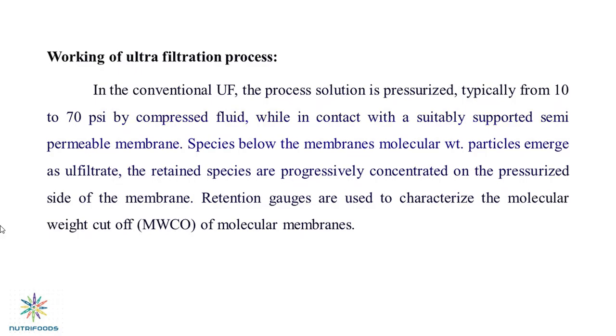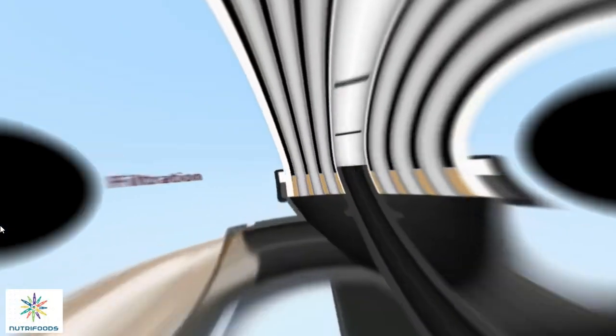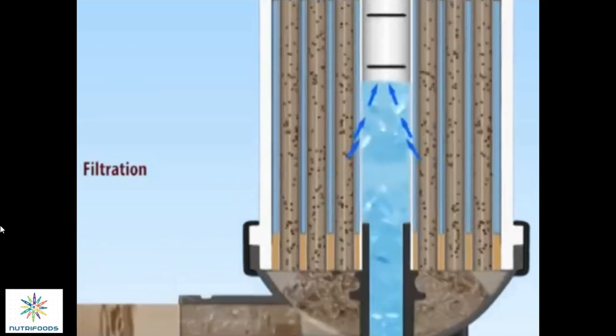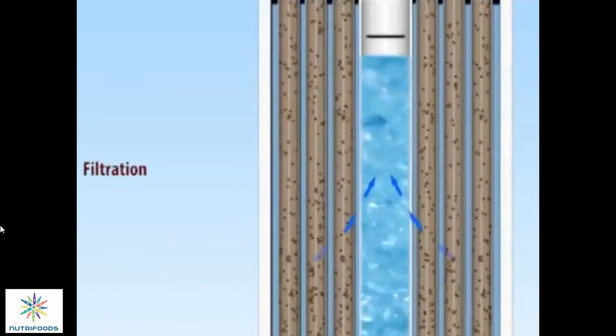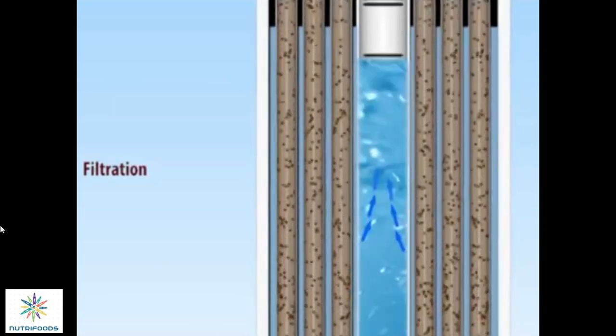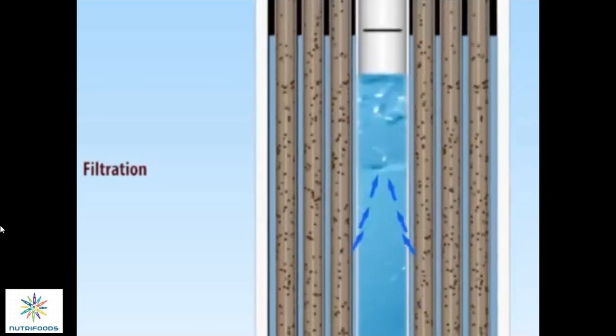In conventional ultrafiltration, the process solution is pressurized, typically from 10 to 70 psi, by compressed fluid. While in contact with a suitably supported semi-permeable membrane, species below the membrane's molecular weight cutoff emerge as permeate. The retained species are progressively concentrated on the pressurized side of the membrane. Retention values are used to characterize the molecular weight cutoff of the membrane.